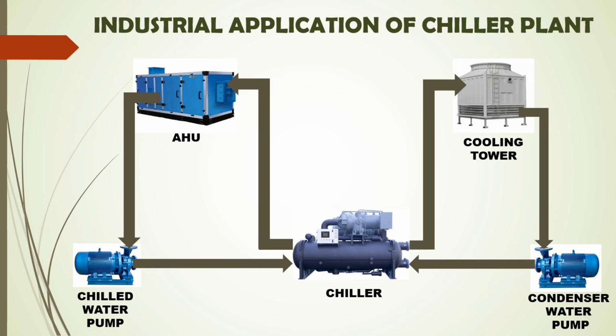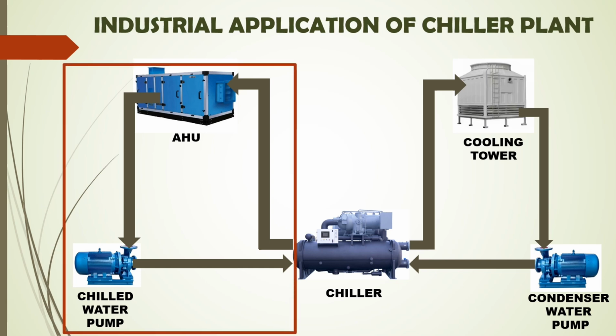A chiller system consists of two main circuits, that is the chilled water circuit and the condenser water circuit. In the chilled water circuit, the AHU and chilled water pump are connected to the evaporator of the chiller. The evaporator of a chiller cools the water using the refrigeration cycle. This chilled water is pumped to the air handling unit. Inside the air handling unit, the chilled water absorbs the heat from the air. As a result, the water temperature rises, and this now warmer water is pumped back to the evaporator where it's cooled again. The process is repeated.